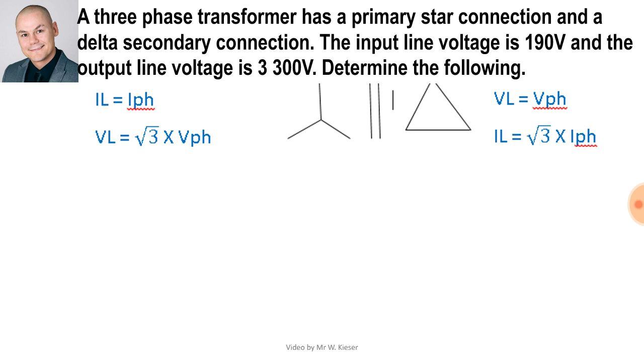A three-phase transformer has a primary star connection and a delta secondary connection. The input line voltage is 190 volts and the output line voltage is 3300 volts. When we see the word three-phase we must remember square root three in our formulas. When working with equations we use phase values, and unless stated we assume line values. On the secondary side, delta connected, VL is equal to V phase, and the voltages given are our line voltages.